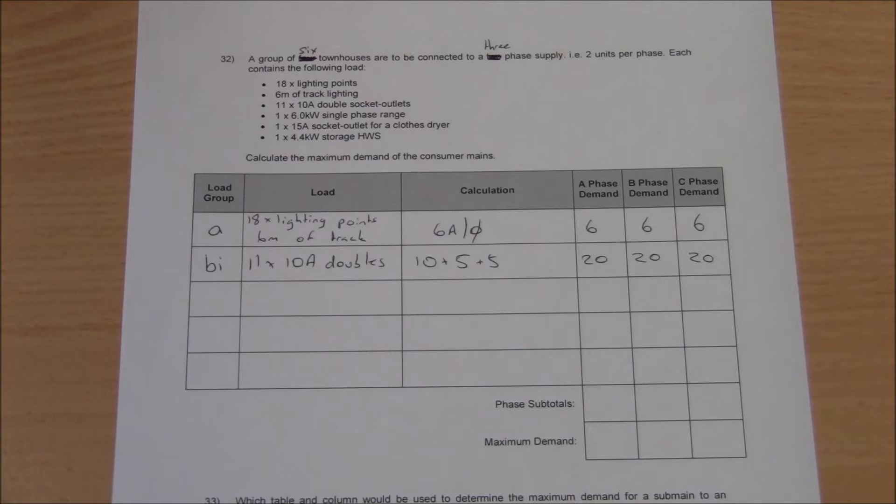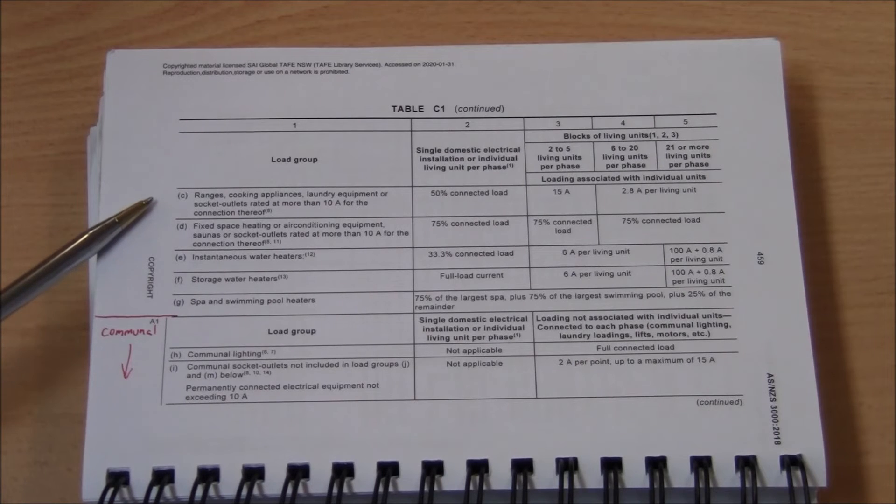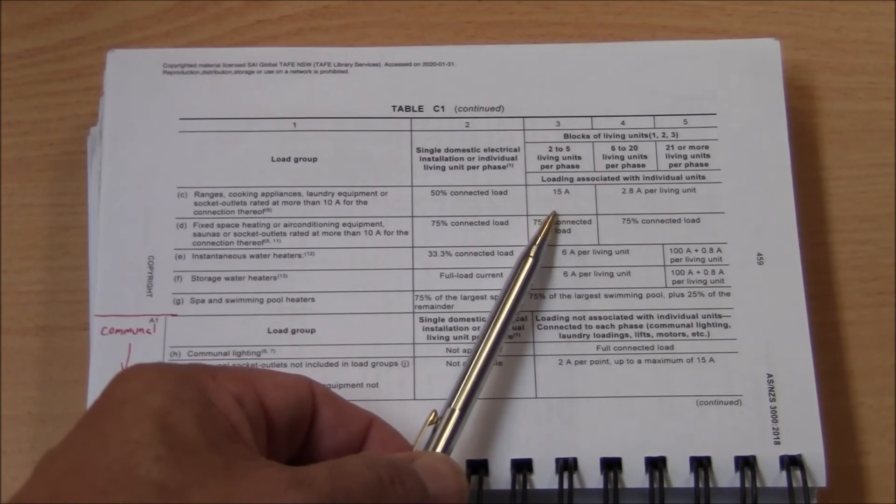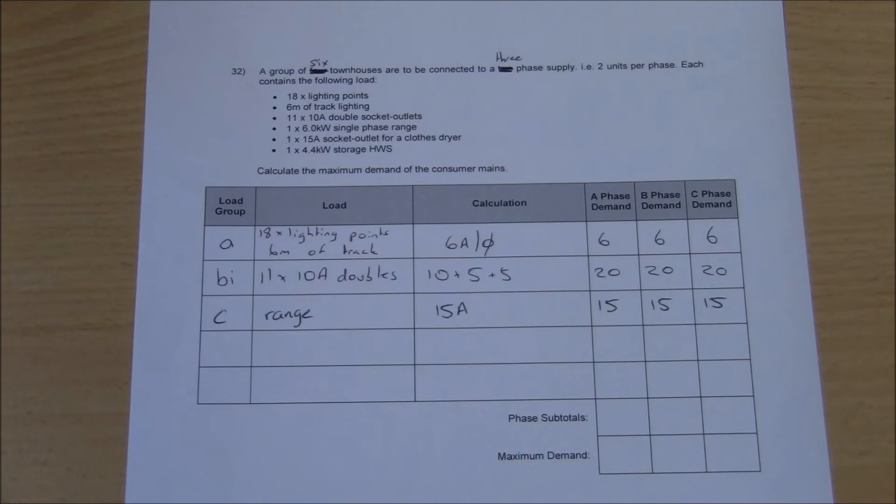Next on the equipment list, each unit has a single phase range rated at six kilowatts. Load group C is the appropriate load group for the range, and once again column 3 indicates 15 amps. While we're on the topic of load group C, we note that the next item, a 15 amp outlet for a clothes dryer, falls under the same group. As such, we've already included it.